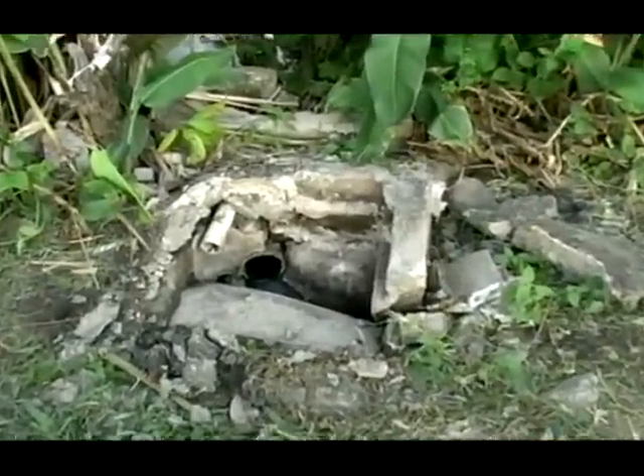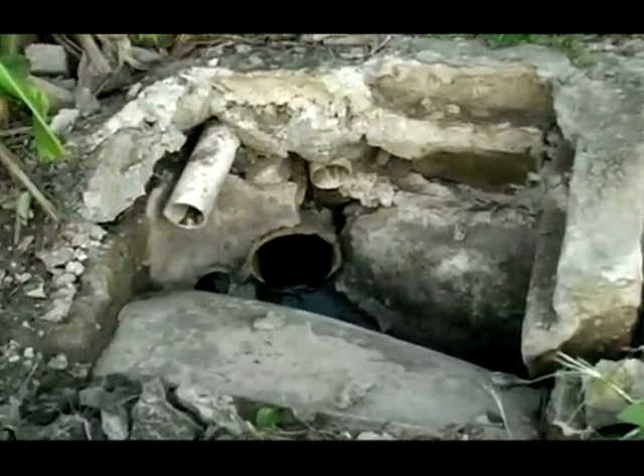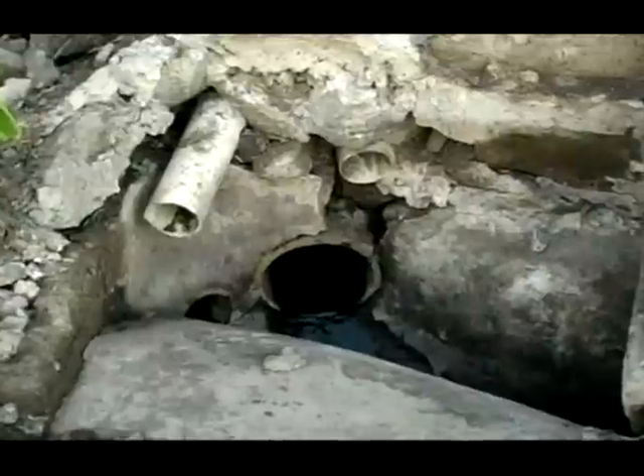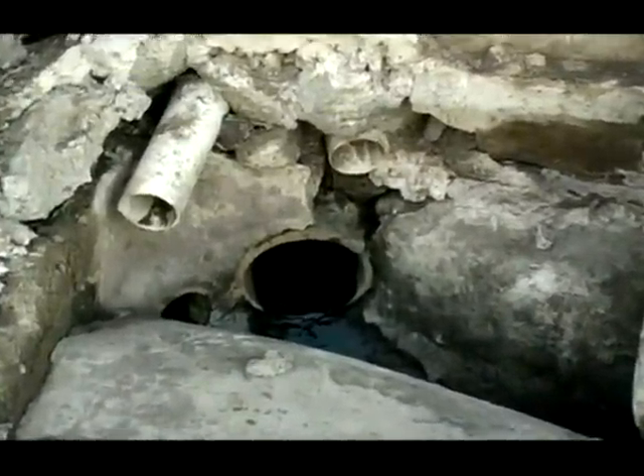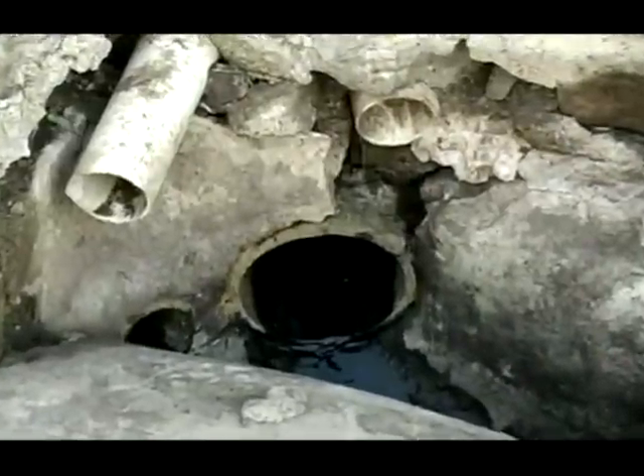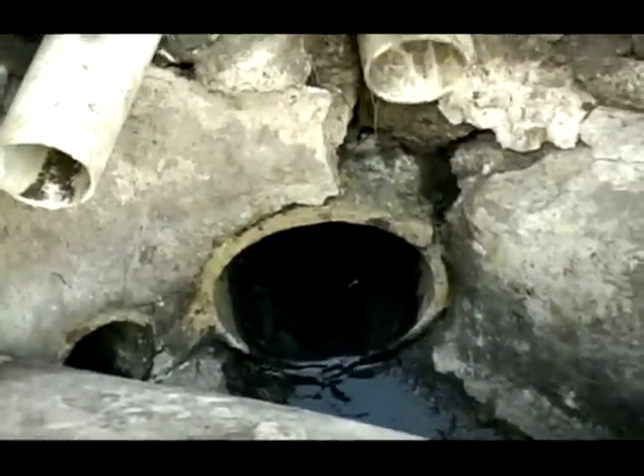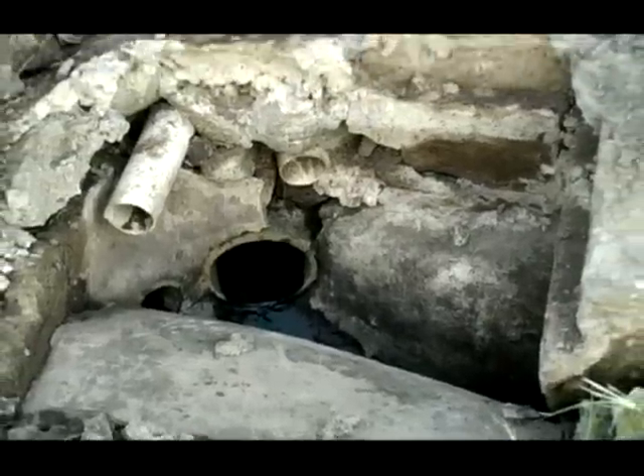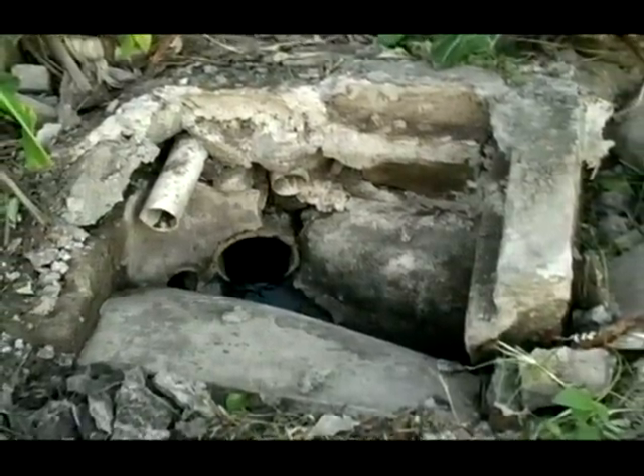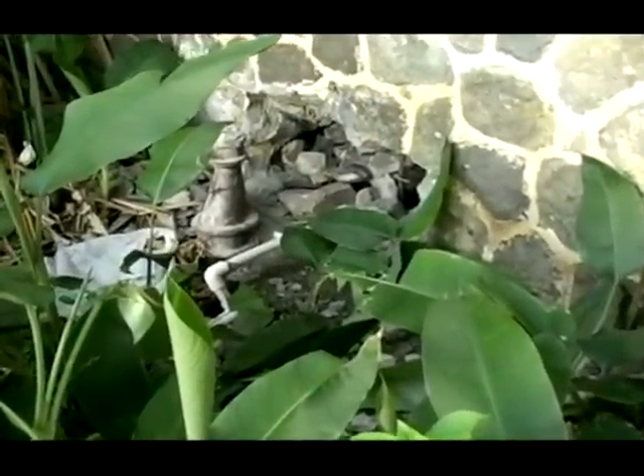Here's another one. What you have here is two sets of pipes — you see the big cast iron pipe at the bottom that brings sewage, and then some smaller ones on top that bring water from the sink. The problem is that sewage and sink water are not supposed to come into the same junction box. As you can see, the junction box is old and crumbling — the worker just ripped it out with his hand — and sewage was right there, blocked, so nothing could pass through.